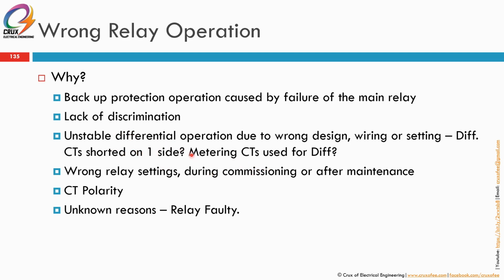There have been cases where a packager, not an electrical switchgear packager, but like solar turbine packages, turbine packages, gas generator packages, install the protection. Sometimes these small packages are not of electrical background. So when they designed a differential protection, there was one case at one of the offshore facilities where they used a metering CT instead of a protection 5P20 or class X CT for the differential protection. Every time the generator started on no load, there was no issue. But when some big load came into the generator, it tripped because the metering CT was saturated.